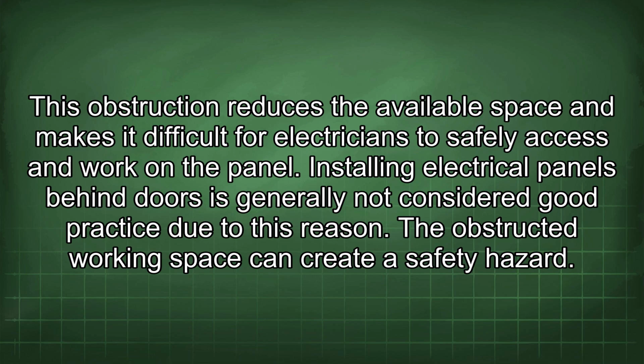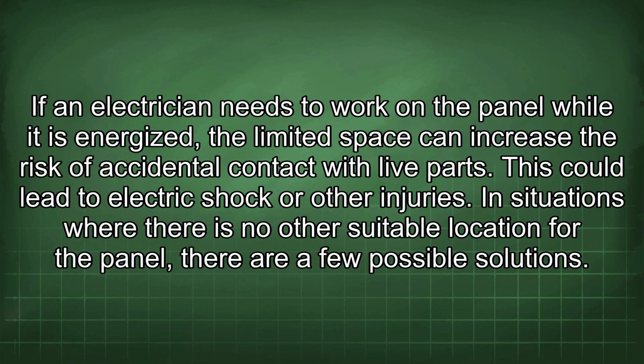The obstructed working space can create a safety hazard. If an electrician needs to work on the panel while it is energized, the limited space can increase the risk of accidental contact with live parts. This could lead to electric shock or other injuries. In situations where there is no other suitable location for the panel, there are a few possible solutions.